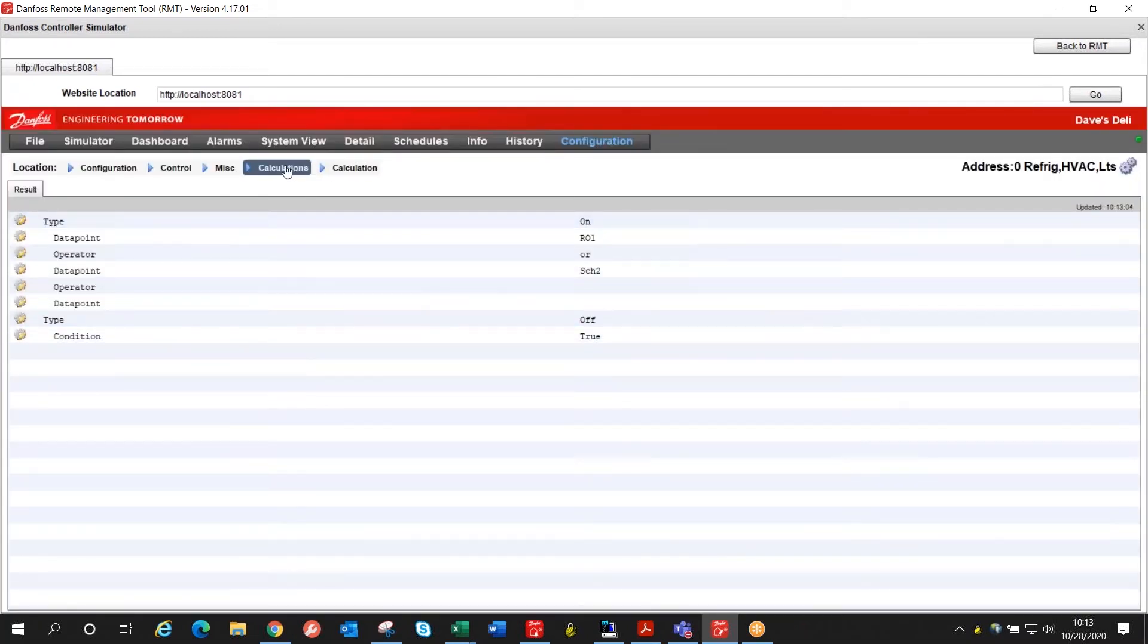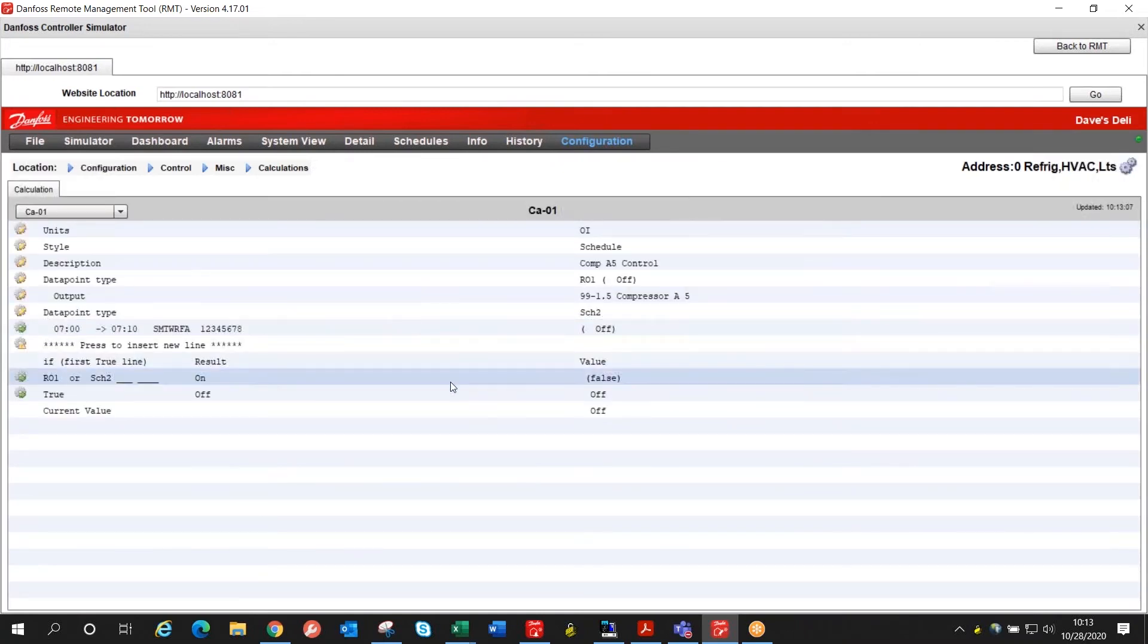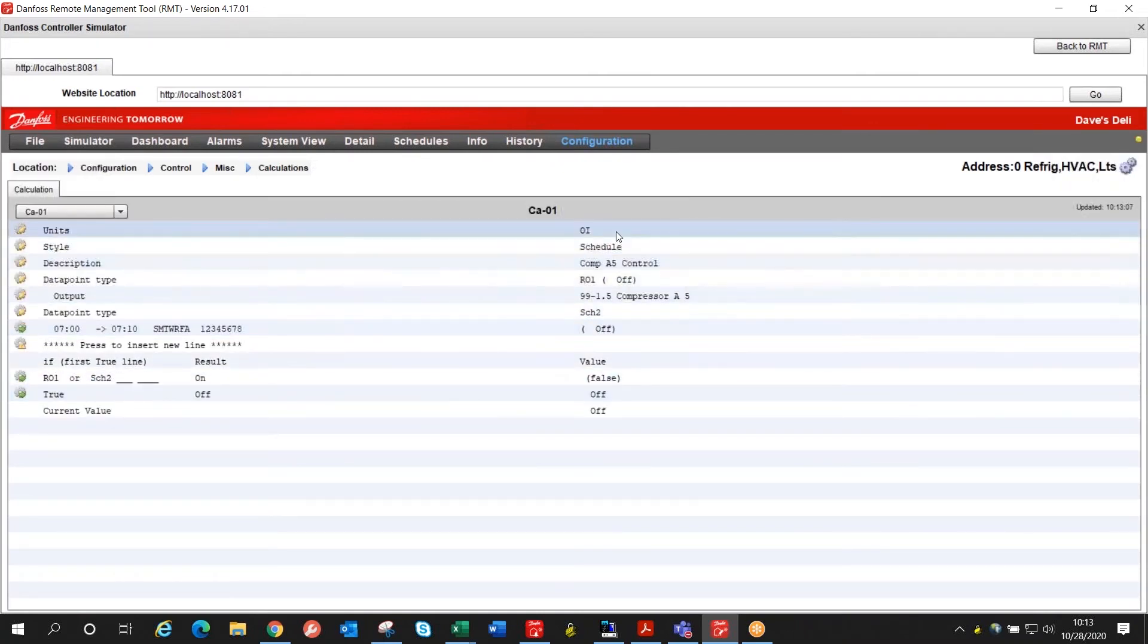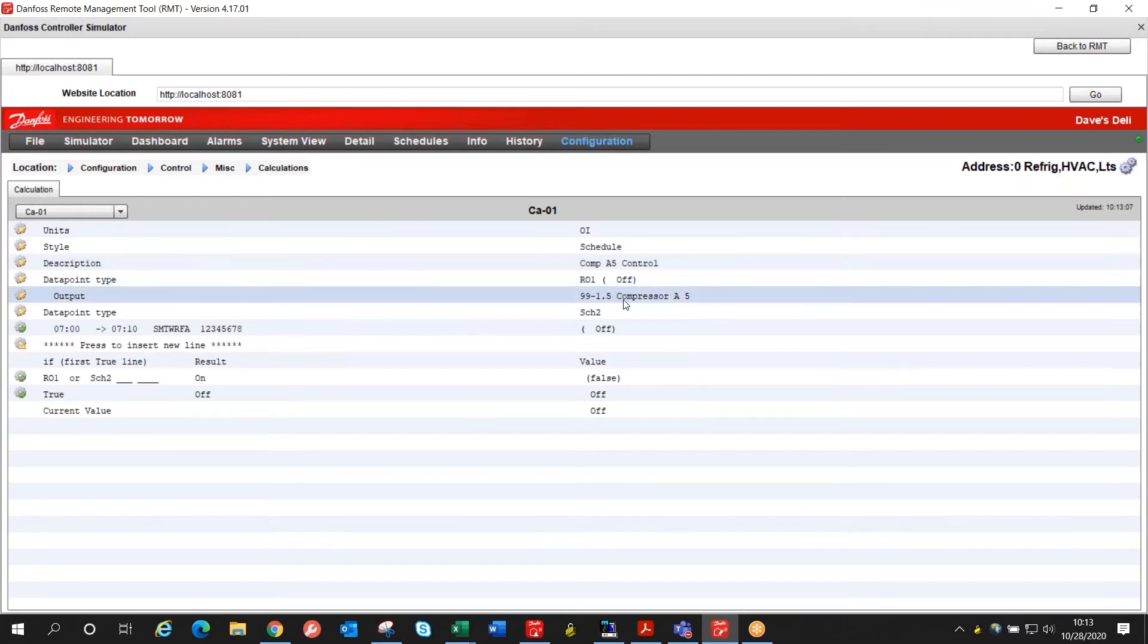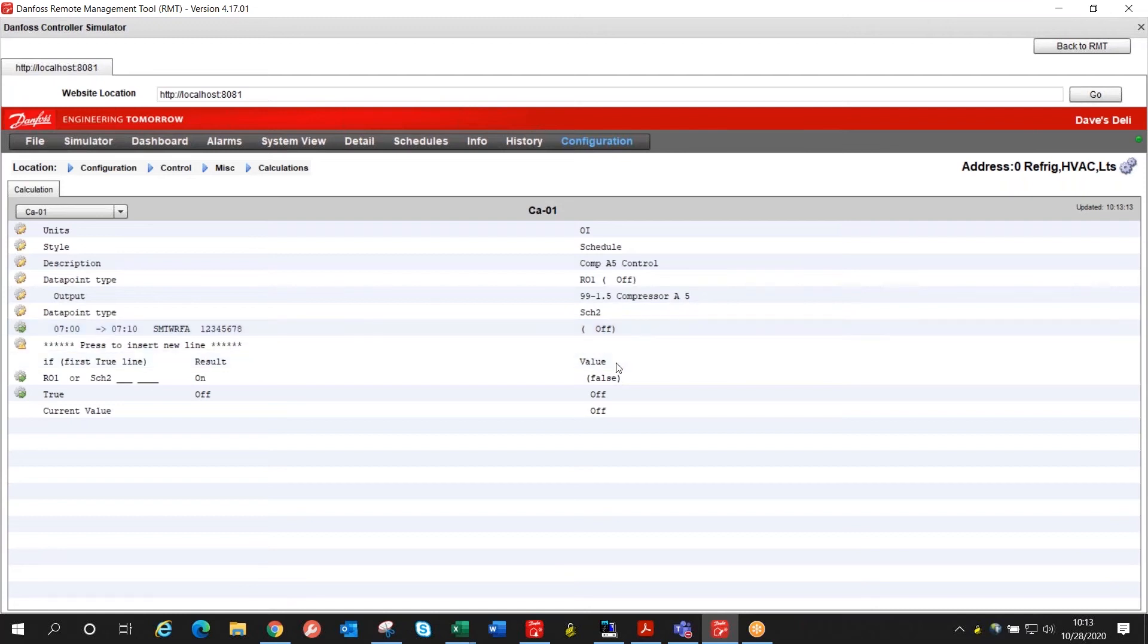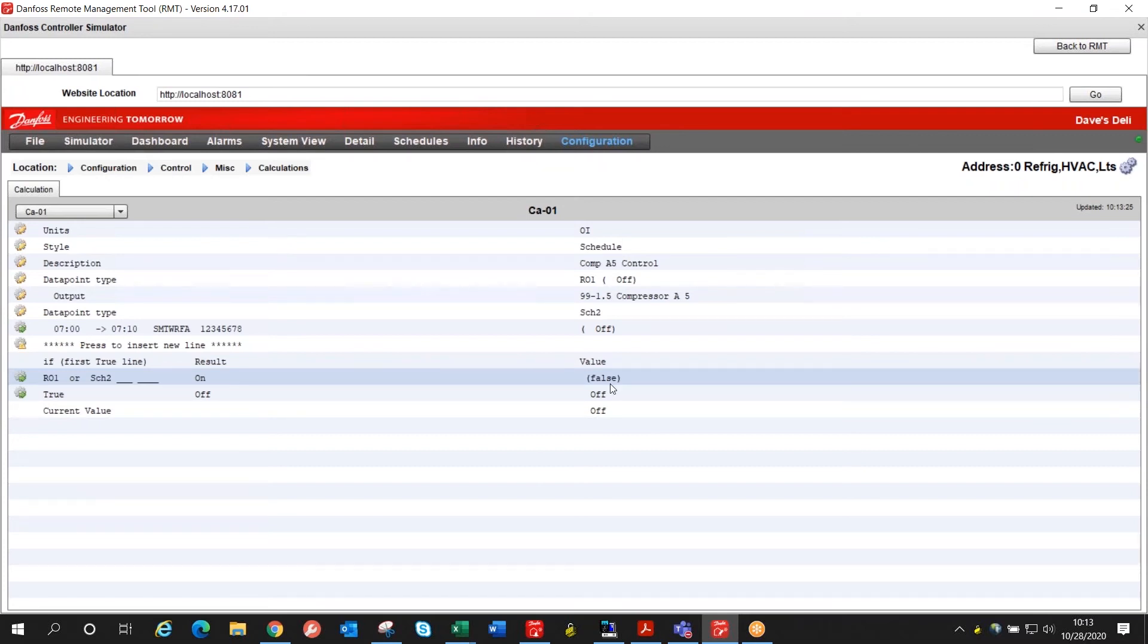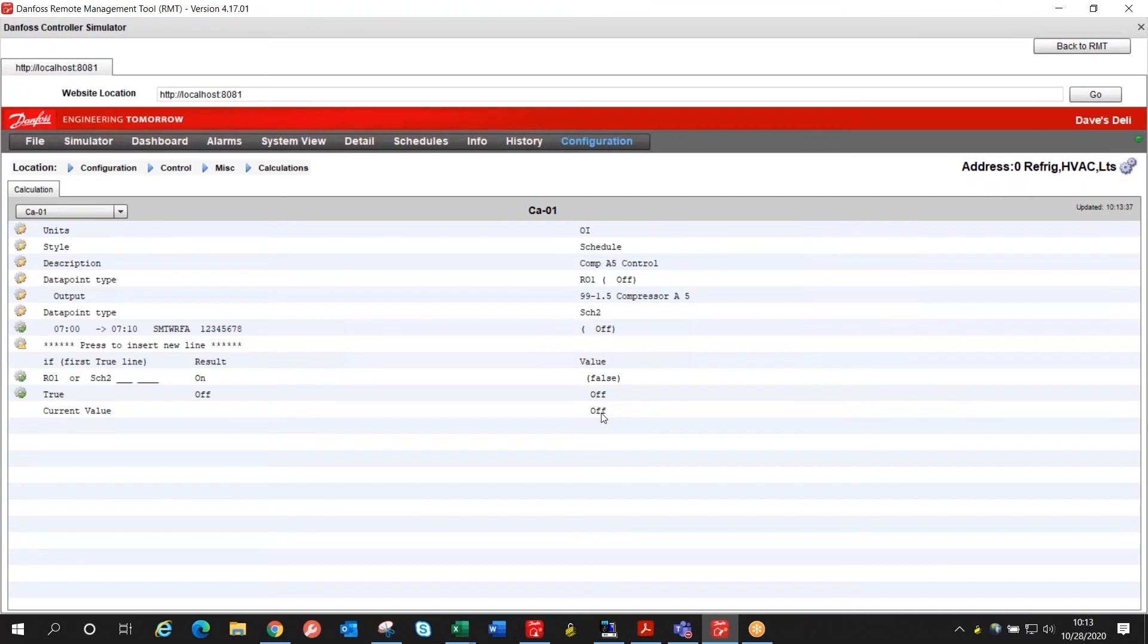And we back up a screen and you'll see how that works. So at the top we set some basic options. In the middle we defined our compressor that we need to look at plus our schedule and then down here in the bottom it will read as relay one which is our compressor or the schedule can be on. If either one of those is true this calculation will switch on and that will turn on the actual compressor relay.